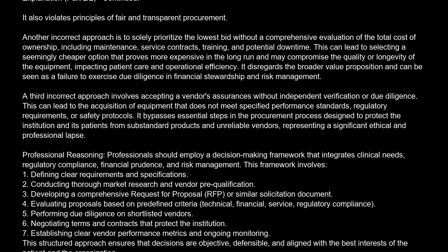Another incorrect approach is to solely prioritize the lowest bid without a comprehensive evaluation of the total cost of ownership, including maintenance, service contracts, training, and potential downtime. This can lead to selecting a seemingly cheaper option that proves more expensive in the long run and may compromise the quality or longevity of the equipment, impacting patient care and operational efficiency. It disregards the broader value proposition and can be seen as a failure to exercise due diligence in financial stewardship and risk management.